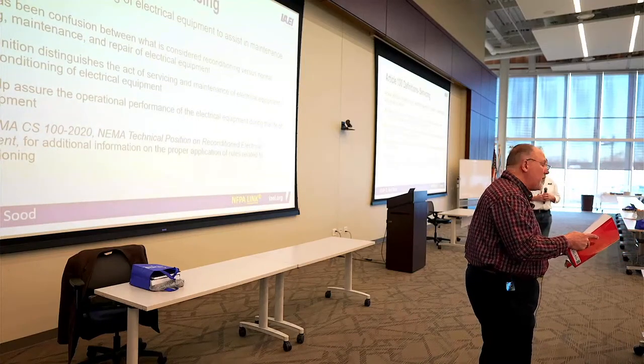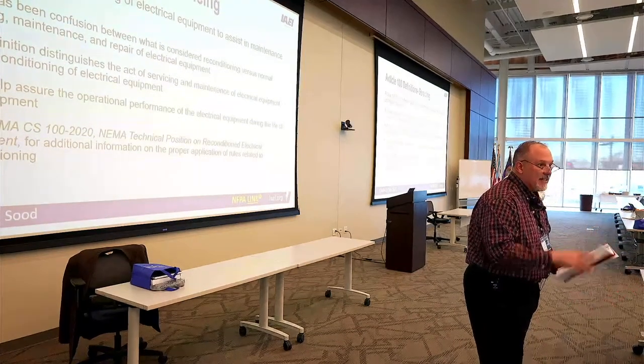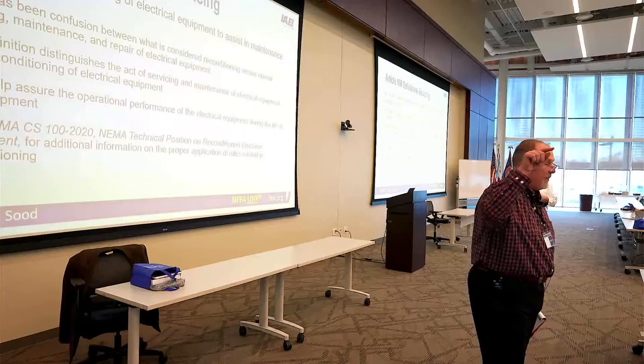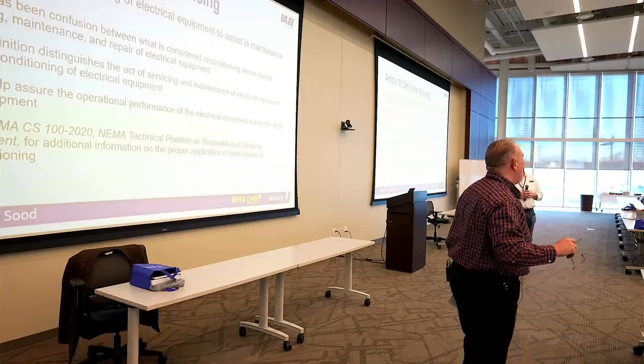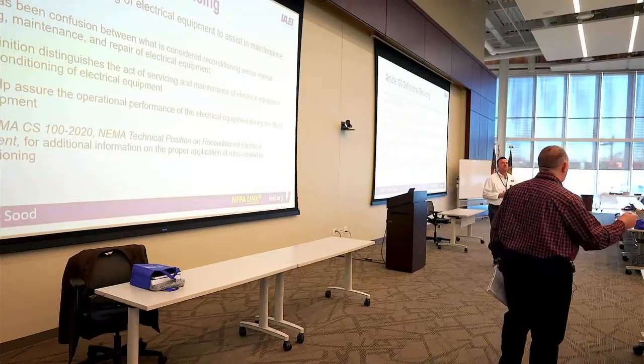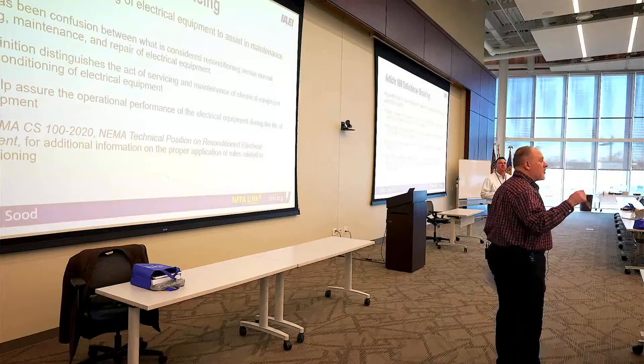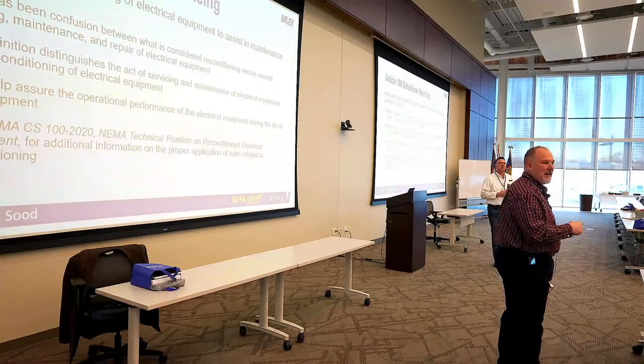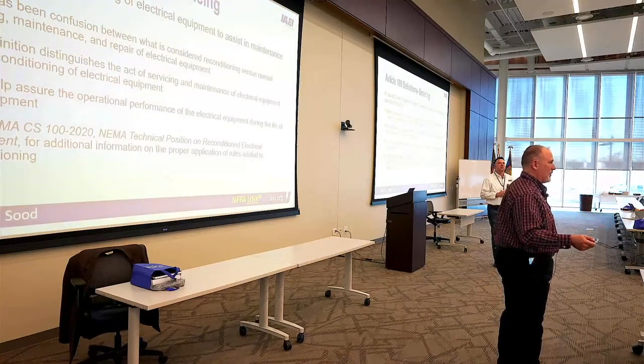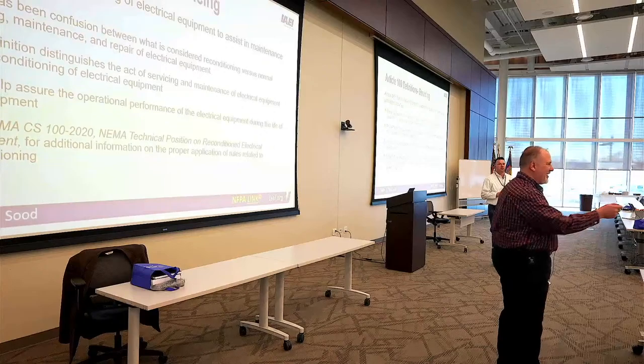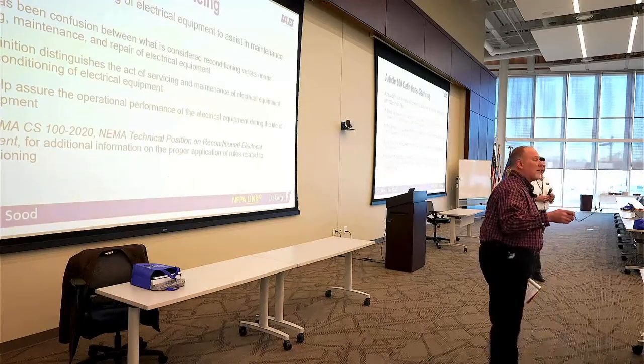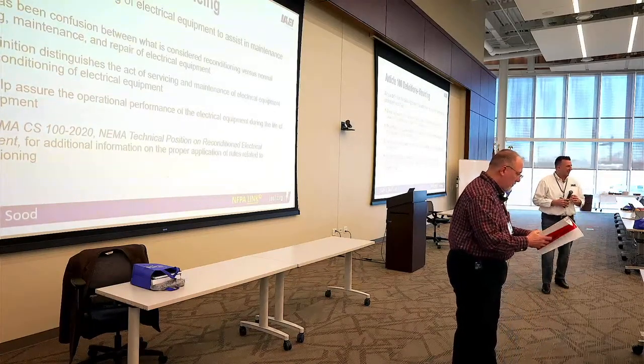A is equipment required to be listed. In some cases, Article 240, I love this one when it went in: we put a requirement that if you recondition a power circuit breaker, it's required to be listed. But at the time, if you bought a new one, it wasn't required to be listed. I know, that's what I said. But in any case, in the 2023, we require all low voltage breakers to be listed.